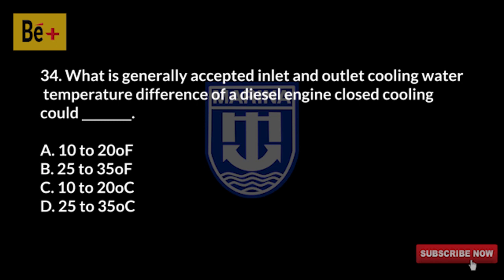What is the generally accepted inlet and outlet cooling water temperature difference of a diesel engine closed cooling system? A) 10 to 20 degrees Fahrenheit, B) 25 to 35 degrees Fahrenheit. The answer is A, 10 to 20 degrees Fahrenheit.